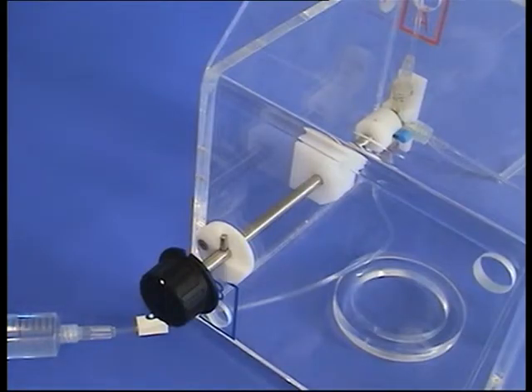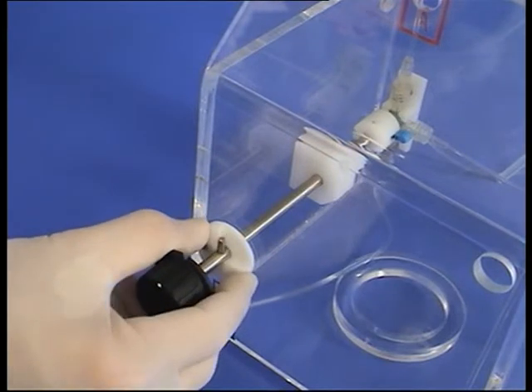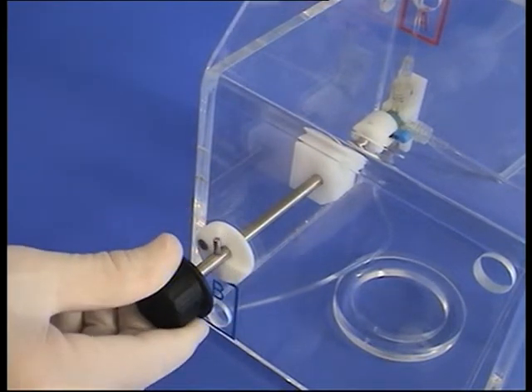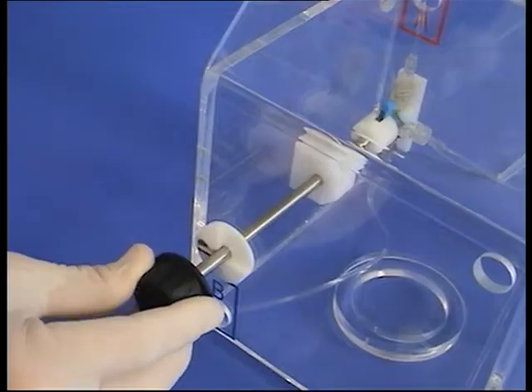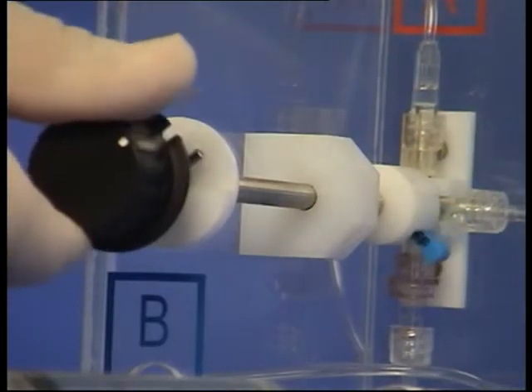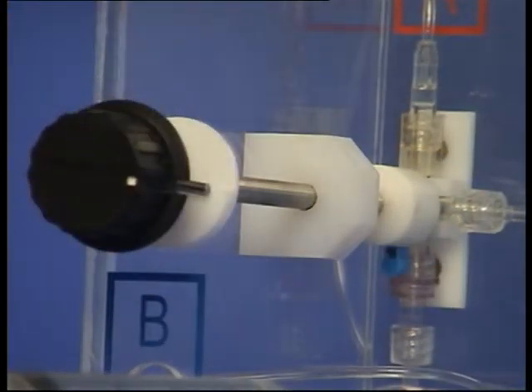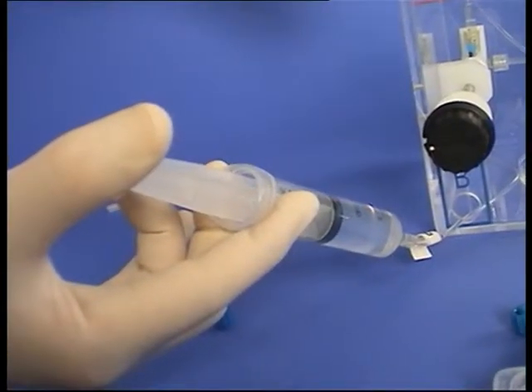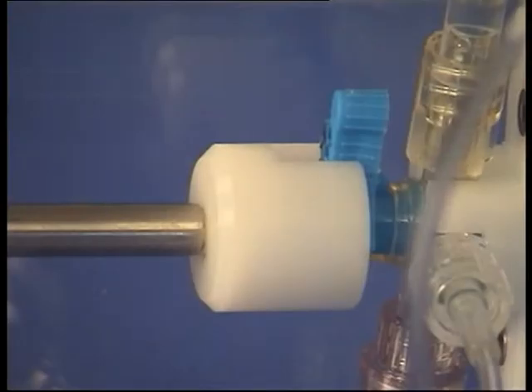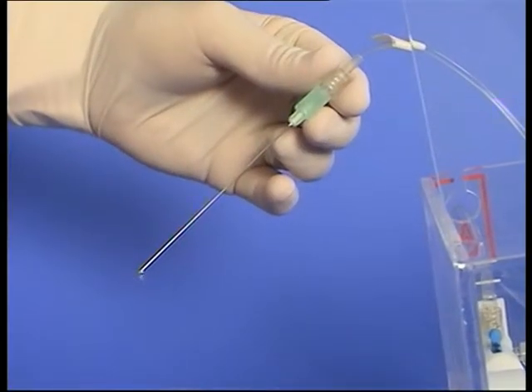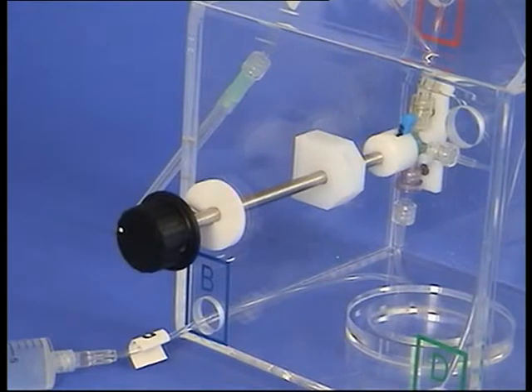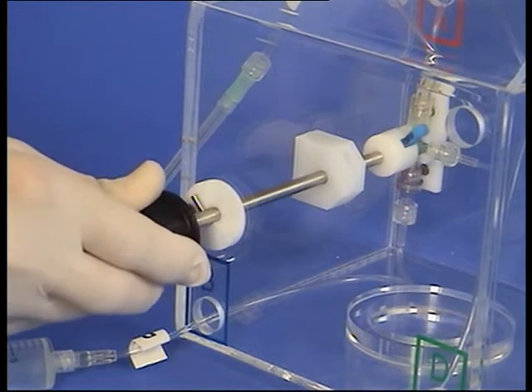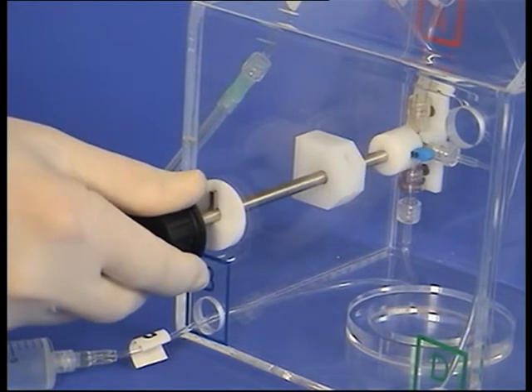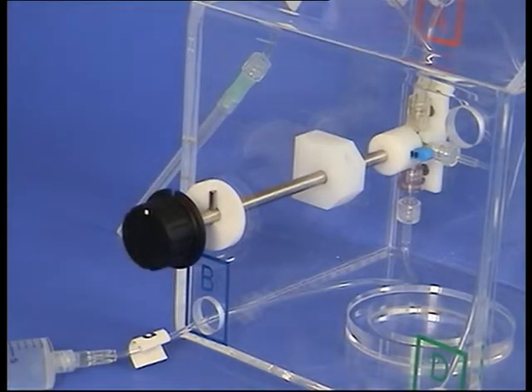Before priming line C, make sure to partially disengage the control knob by pulling it back past the notch. This will allow for a 180-degree rotation of the handle of the 3-way stopcock. To prime line C, the handle of the 3-way stopcock needs to be at the 12 o'clock position for water to flow through the stopcock and into line C. Before continuing with the rest of the setup, it is vital to ensure that the control knob is back into its original position and that the 3-way stopcock is fully re-engaged.